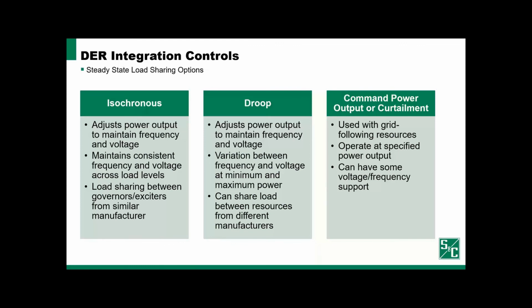Okay, not sure what that was, but moving along, there are two different ways that we handle these load changes, and both of them are with grid forming resources. Grid forming resources attempt to maintain voltage and frequency output as opposed to maintaining a constant power. One of those grid forming approaches is isochronous. Isochronous controls try to maintain a constant frequency and a constant voltage across various load levels.